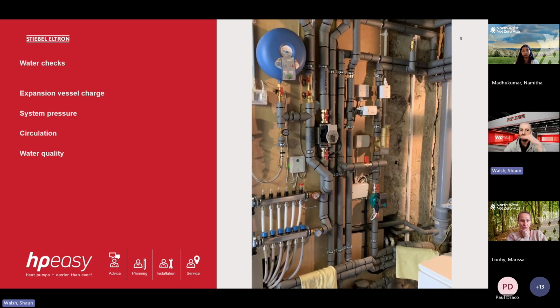Once we're satisfied water quality is up to standard, there's a few other things that we should check when we're on site that could potentially cause issues. So, expansion vessel charge. Just up here, you can see there's an expansion vessel. The job of this is to maintain system pressure and make sure that it doesn't get too high. As we're heating up, the water will expand, and the expansion vessel's job is to take up that expansion. If it was to get too high, generally over 3 bar, it would discharge the water in the system and keep the system under low pressure. Okay. These need to be checked on an annual service. They hold a specific charge, and usually written on the side of them, it will tell you what the charge should be. The next thing would be the actual system pressure itself.